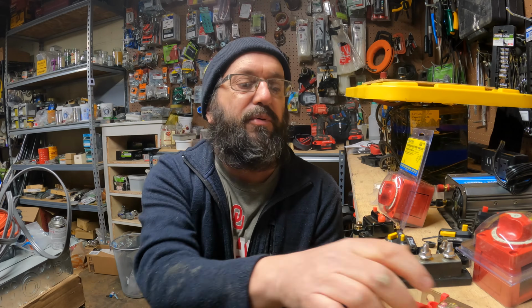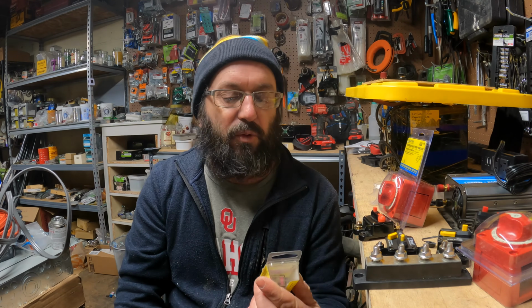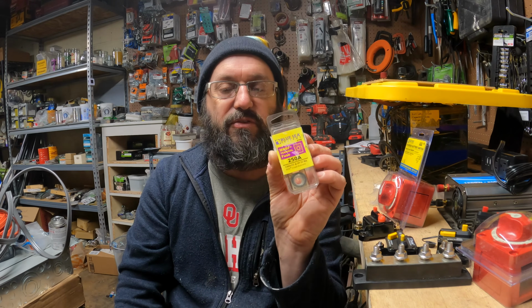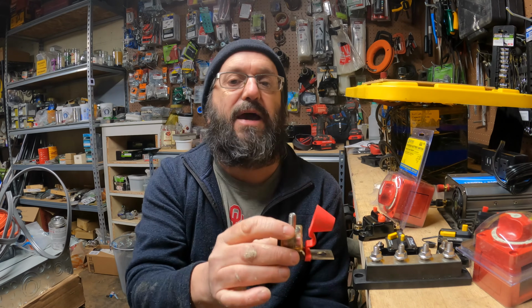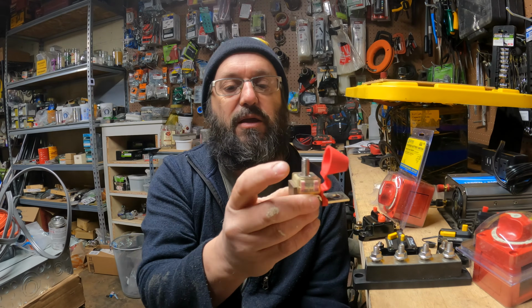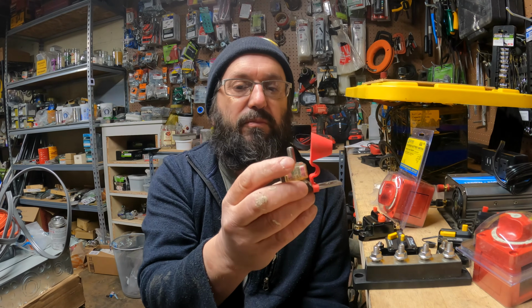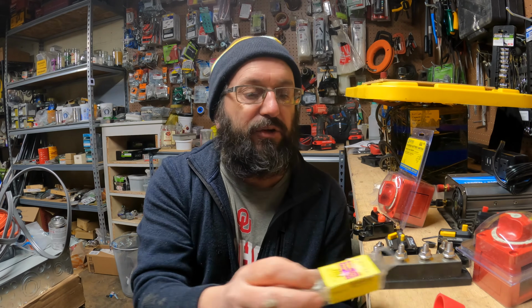On my system, because my batteries are in parallel, I put a terminal fuse, one of these MRBF fuses, on each battery in my battery bank. That way, if there's a failure in the battery bank, the fuse will catch any potential problems. This isn't something you need to do if you have stuff in series, but if you have stuff in parallel, you definitely want to put these on there.